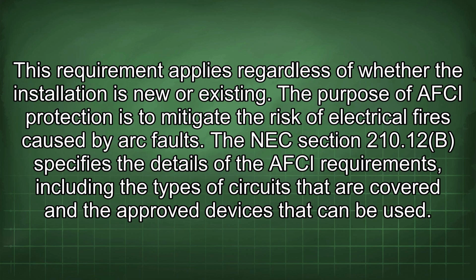This requirement applies regardless of whether the installation is new or existing. The purpose of AFCI protection is to mitigate the risk of electrical fires caused by arc faults. The NEC Section 210.12(B) specifies the details of the AFCI requirements, including the types of circuits that are covered and the approved devices that can be used.